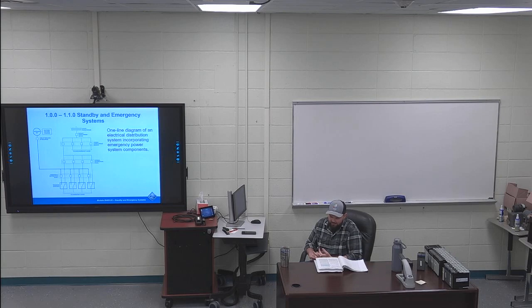But my first highlight on page 1 is on the right hand side of the page, right after those bullet points. The first paragraph is highlighted. In the event of a failure of the normal power supply, emergency lighting, emergency power, or both must be available within the time required for the application, but not to exceed 10 seconds. So it has to happen within 10 seconds for these standby emergency systems.